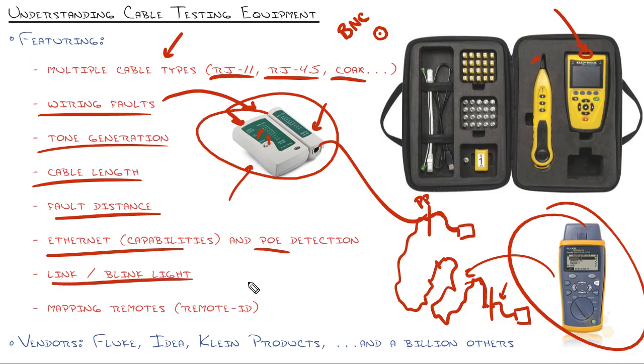Some testers have the ability to link and blink the light. Normally, to tone a cable out you have to disconnect it from the switch, which can be disruptive. Instead, the network tester can cause the link light to go up and down repeatedly, so you can look at the switch, see that light blinking on and off, and quickly identify where it's plugged in.